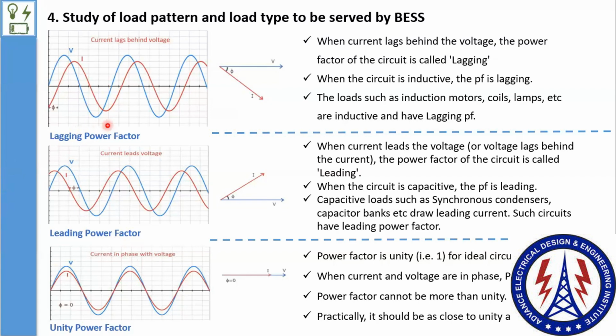When you are feeding to the grid, the point is your power conversion systems or PCU units are technologically enhanced such that, similar to the inverter, they are not producing any power factor issue when releasing the AC output. But next to it there are again cables, transformers, switchgear parts, till the injection point. Because of that, there are ups and downs in your power and power factor, and that triggers the stated limits, which you need to manage.